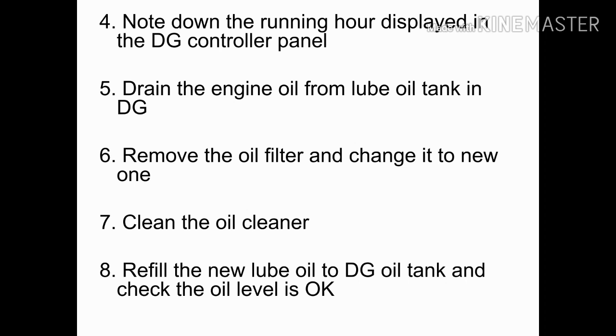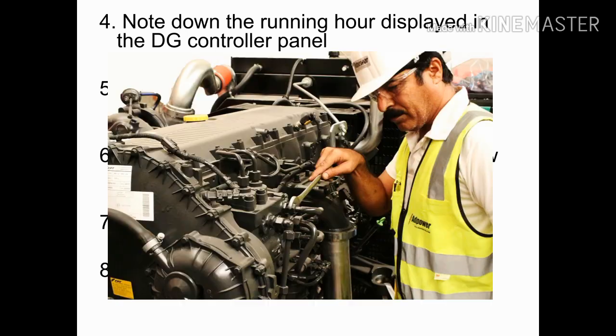The first process is draining the engine oil from the lube oil tank. After 400 running hours, the DG lube oil color typically turns black. Every 400 hours, the first task is to drain the old lube oil from the tank and refill it with new lube oil.